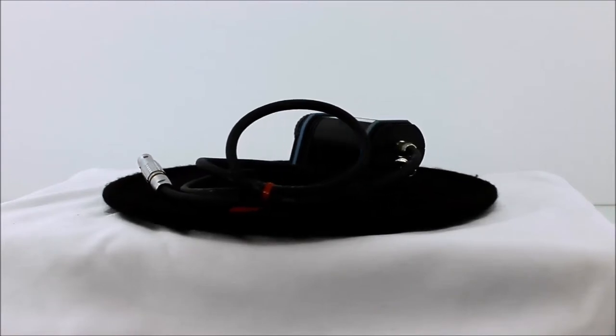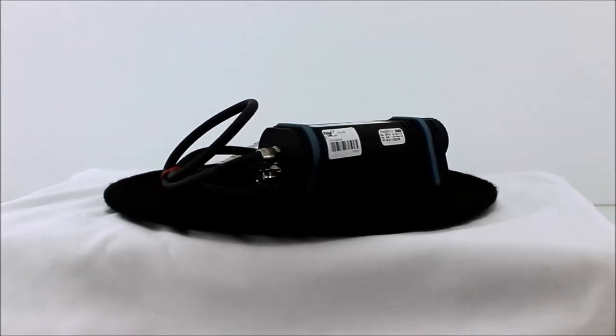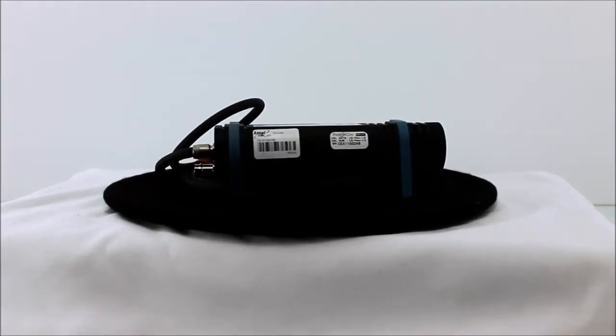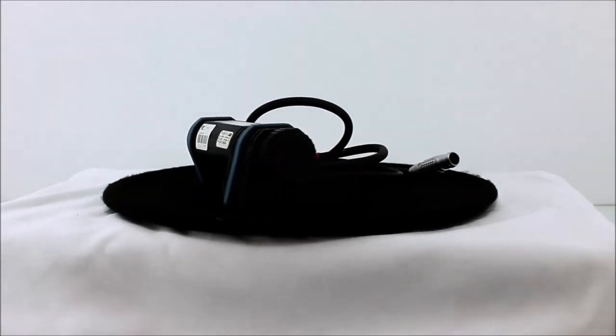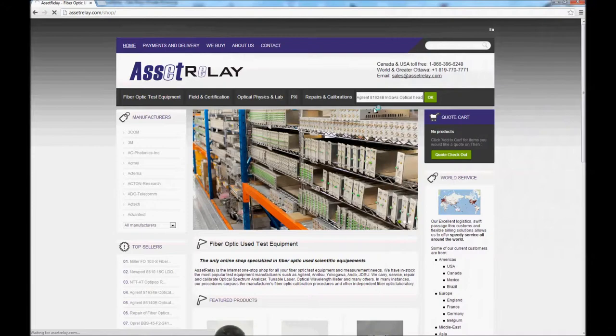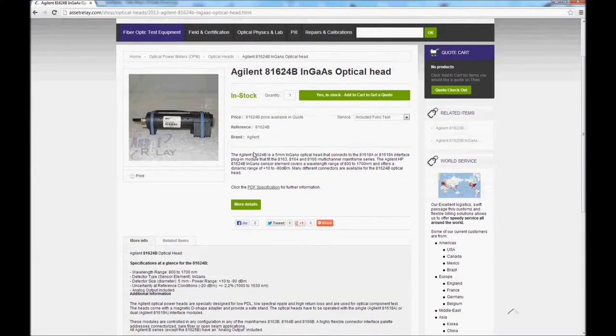It is to be used with the 8163, 8164, or 8166 multi-channel mainframe. The Agilent HP 81624B InGaAs sensor covers a wavelength range of 800 to 1700 nanometers and offers a dynamic range of plus 10 to minus 90 dBm.